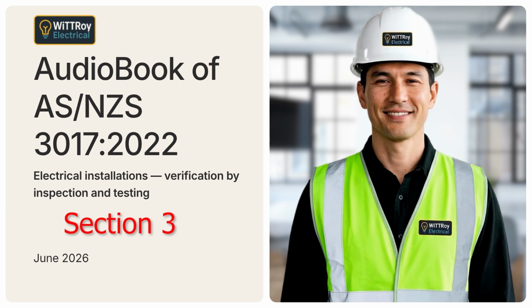Clause 3.3 Checklist. Clause 3.3 gives a guide to the matters that should be checked during visual inspection. The checklist is representative. This means it gives important examples, but it is not limited to only those items. The actual inspection must suit the installation, the work carried out, and the applicable requirements. First, the general safety items need to be checked. Basic protection should be checked. Basic protection means protection against direct contact with live parts. In simple terms, live parts should not be accessible where they can be touched. This may involve insulation, covers, barriers, or enclosures.